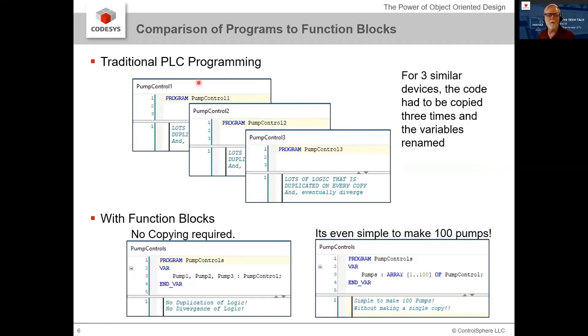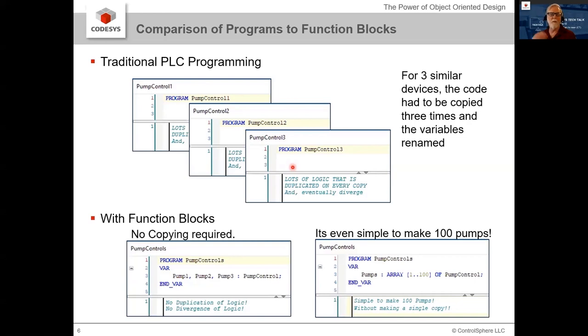Originally, if we created a program to control a pump, we'd create some global variables, write a program, and use those global variables. But when we needed to control two pumps, we'd have to duplicate the global variable list, come up with a naming convention, copy the program, and rename all the variables. Then we'd figure out why it doesn't work because we forgot something, or get a call at midnight because some aspect wasn't updated. And for a third pump, you'd go through that whole process again. Some people created spreadsheets and automation to help, but IEC 61131-3 function blocks are really the best solution.